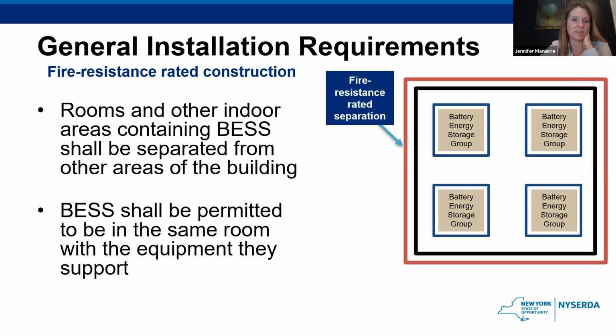Fire resistance rated construction. So any room or other indoor area containing energy storage needs to be separated by a firewall from other areas of the buildings. In certain cases, energy storage is allowed to be in the same room with the equipment they support, but generally speaking, they're going to be separated and closed off.